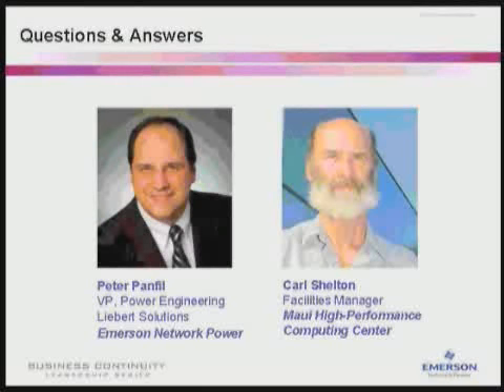Well, we're continuing to design compact rack-based UPS modules that meet the requirements of high-density racks and rooms. It wasn't too long ago that the high end of our rack-mounted UPS range was 3 kVA. Now it's 10 kVA or even higher capacities on the horizon. In larger units, we're moving toward rack form factor UPS modules to provide greater application flexibility.